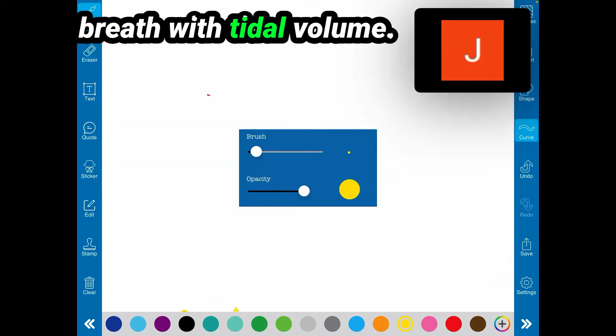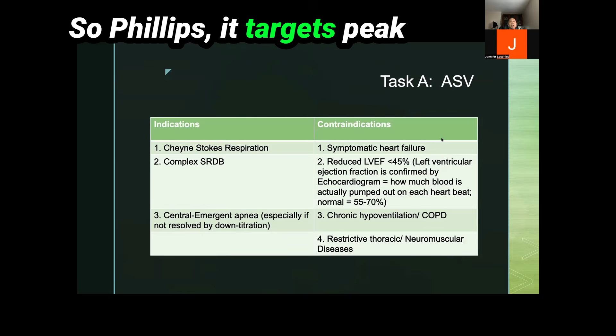Because the patients can be given an assured breath with tidal volume. When you use ASV, you will only use EPAP, minimum pressure support, and maximum pressure support. Auto ASV or ASV auto, you will use minimum and maximum pressure support and minimum and maximum EPAP. So it's very tricky, but yeah, it works. Philips targets peak flow. And then ResMed targets minute ventilation.